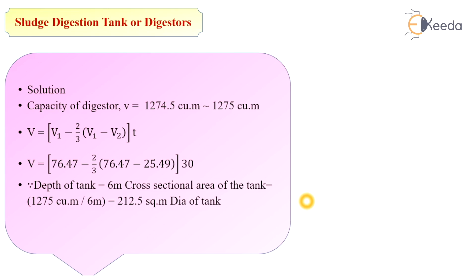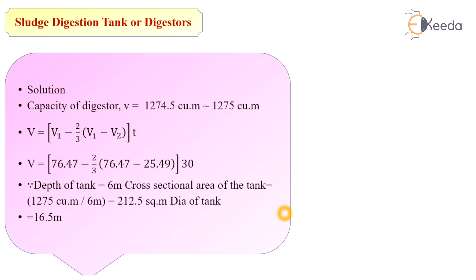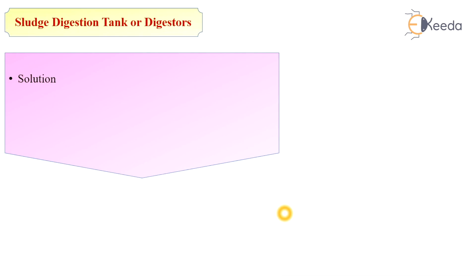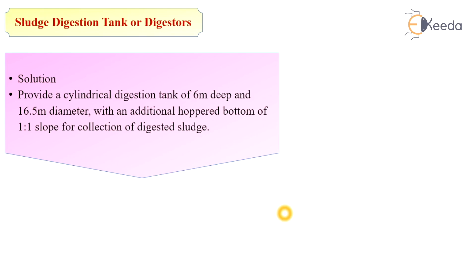Assuming the depth of the tank as 6 meters, the cross-sectional area equals total volume divided by depth = 1275 / 6 = 212.5 m². From this, the diameter of the tank is calculated as 16.5 meters. Therefore, we will provide a cylindrical digestion tank of 6-meter depth and 16.5-meter diameter, with an additional hopper bottom of 1:1 slope for collection of digested sludge.